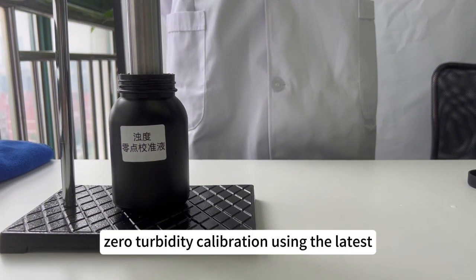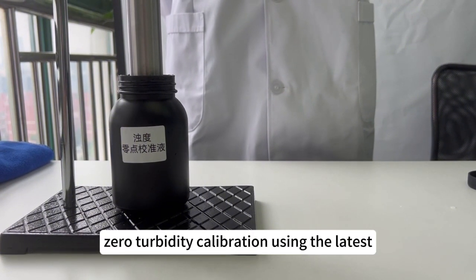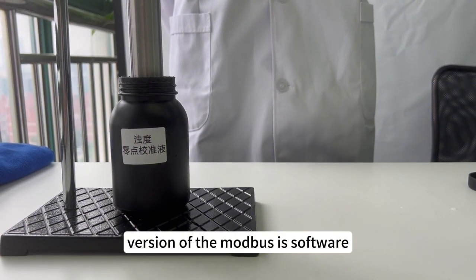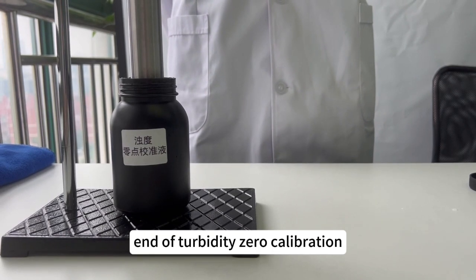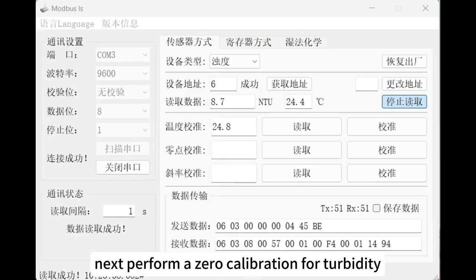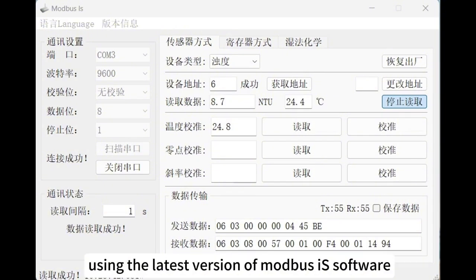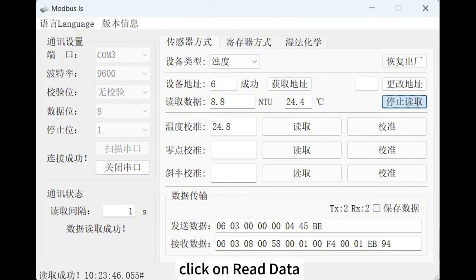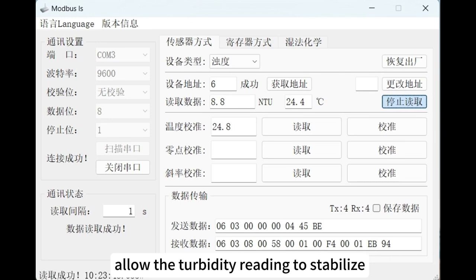Then perform a zero turbidity calibration using the latest version of the Modbus IS software. End of Turbidity Zero calibration. Next, perform a zero calibration for turbidity using the latest version of Modbus IS software. Click on Read Data. Allow the turbidity reading to stabilize.